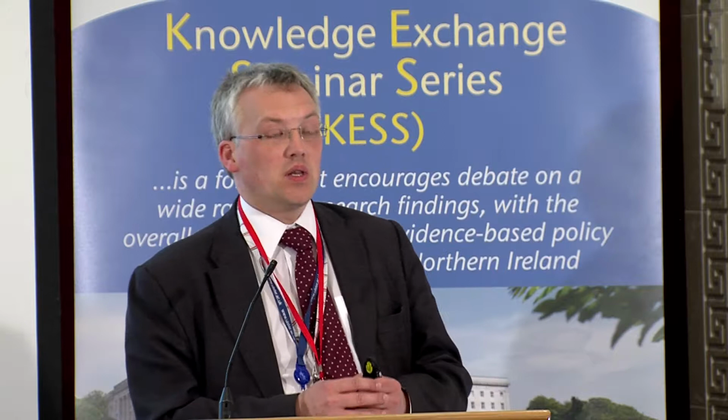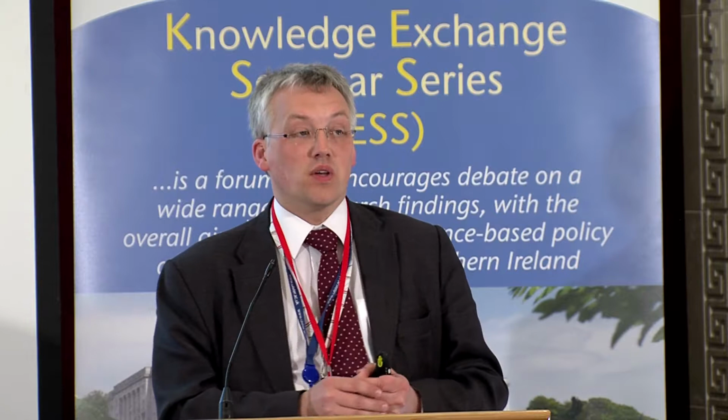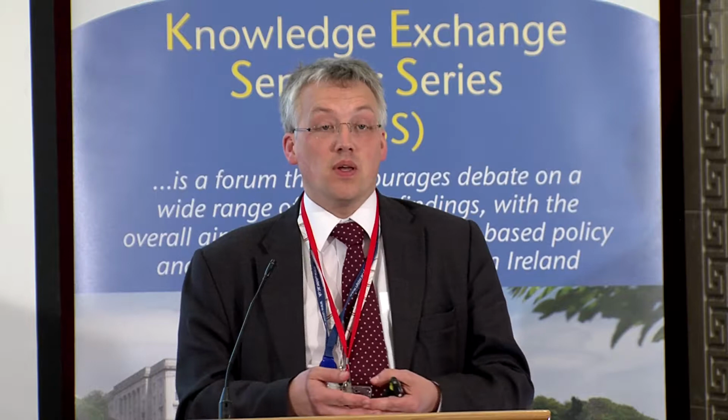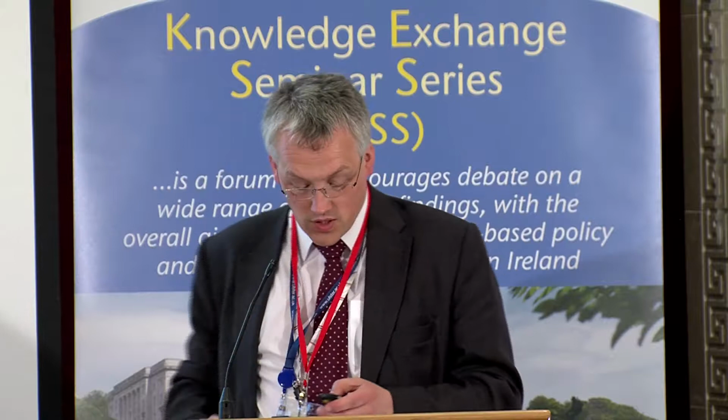So if demand goes up, the frequency drops. If demand goes down, the frequency rises. If I put on a kettle in Coleraine, and I've got a strong enough meter on the system in Cork, I should actually register the drop in the frequency as a result of that. That's how sensitive the system is. So how do we cope with it? Well, this man sitting in Castlereagh has a big dial in front of him that tells him what's happening. As demand goes up, he demands more power stations come on stream, and he is there trying to make sure that that 50 mark stays the same.